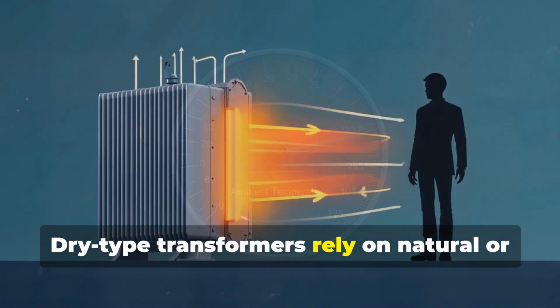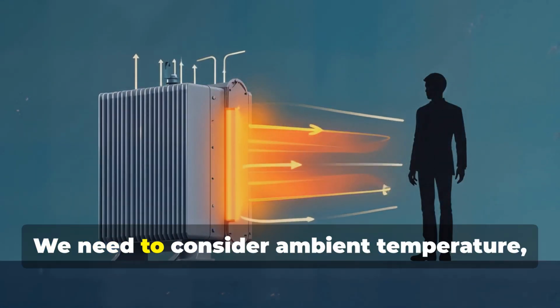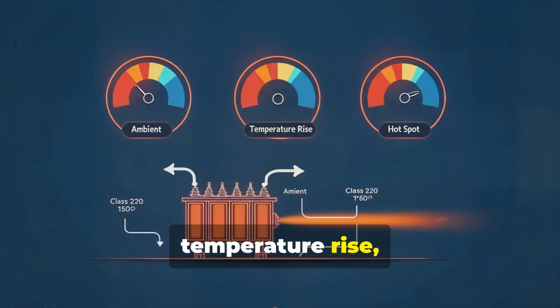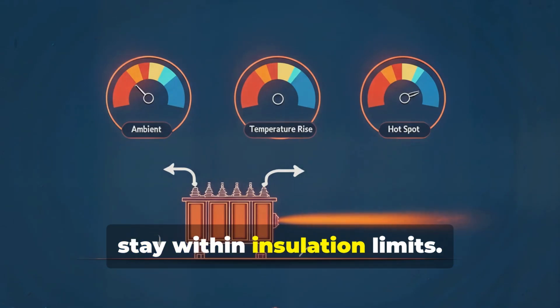Temperature control is critical. Dry-type transformers rely on natural or forced air cooling. We need to consider ambient temperature, temperature rise, and hotspot temperature to make sure we stay within insulation limits.